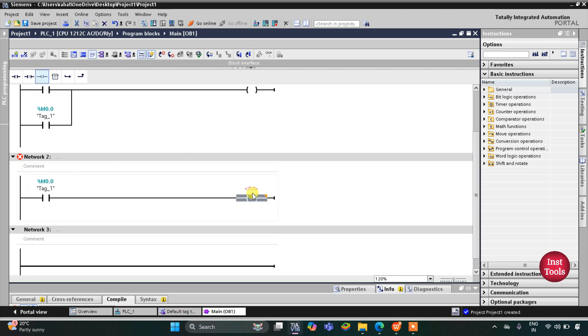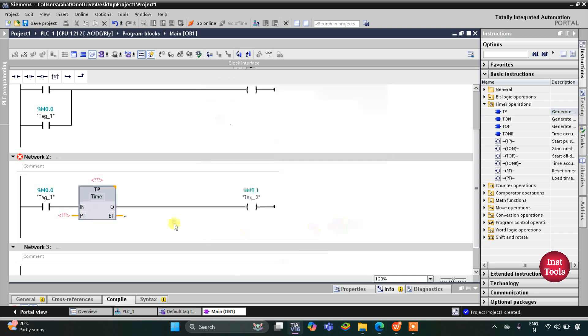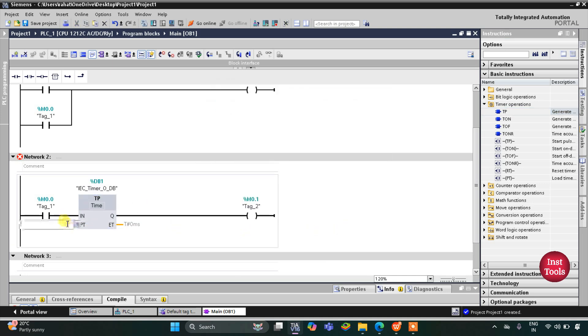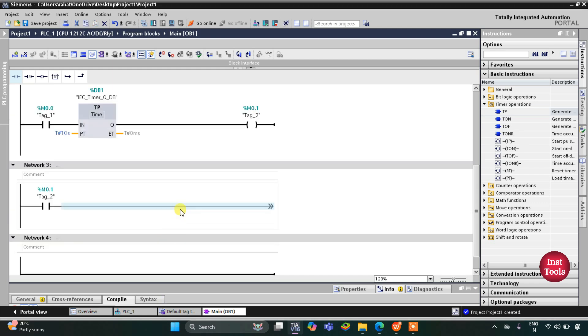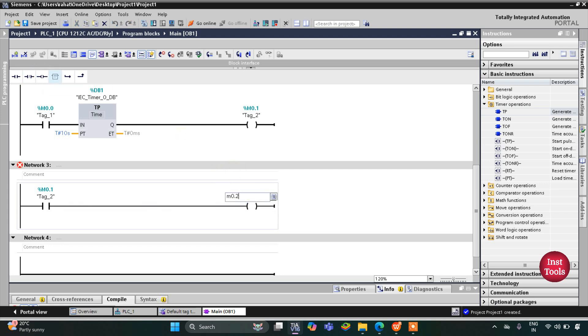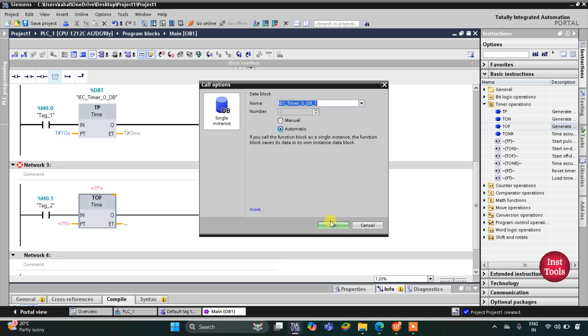When M0.0 gets true, one more memory bit M0.1 gets true. M0.1 should remain on for 10 seconds only, so I will use a pulse timer TP with a preset value of 10 seconds. When M0.0 gets true and M0.1 gets true, one more memory bit M0.2 gets activated. After 10 seconds M0.1 gets off, but M0.2 should remain on for 60 seconds using an off-delay timer T-OFF with a preset of 60 seconds.